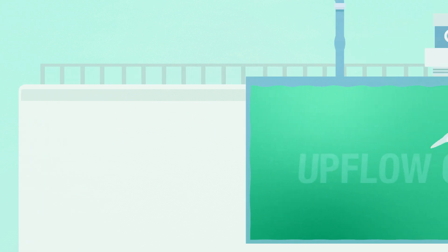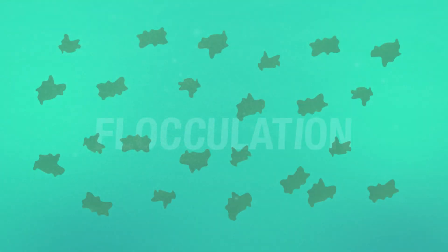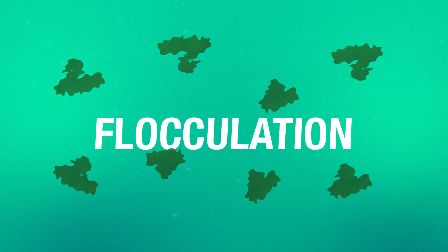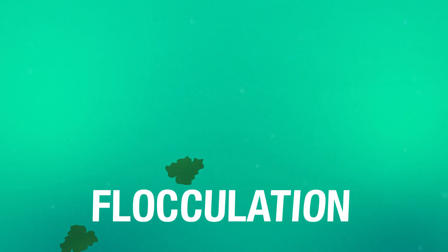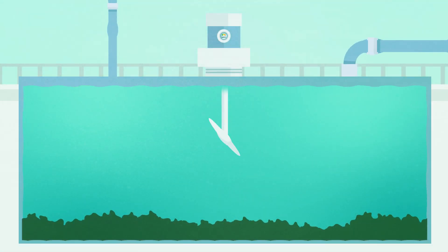The water first enters the upflow clarifier where clarification takes place. A positive charged chemical is mixed with the raw water to start the coagulation and flocculation process. During this process, solids in the water that have a negative charge bind together with this chemical, becoming heavy, and fall to the bottom. This process leaves a layer of solids called floc at the bottom with clear water on top.